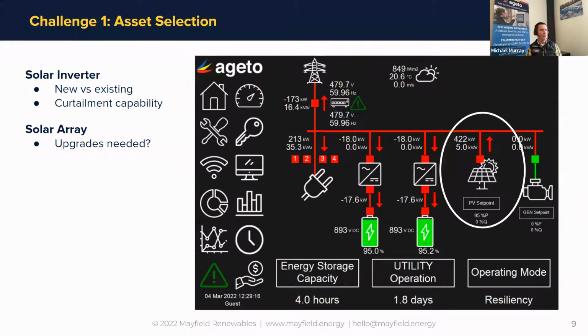I did see a couple questions on microinverter usage. Ageto does not yet have any project with microinverters. Typically they don't have the curtailment and control capabilities built in from the factory, though I know that's being worked on for a few of these different microinverters. What is possible is to use contactors to segment off parts of the solar array, basically opening the contactor so we can't get any more power from those PV microinverters, which allows us to modulate the output of the solar array. It's not as precise as curtailment commands over Modbus, but it's a way to make it work.